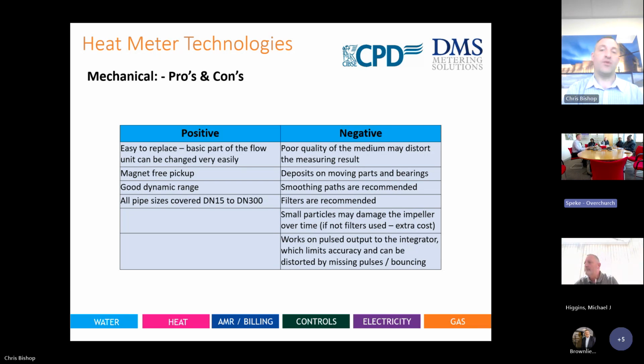With regards to the pulsed output integrator, if you have a high voltage cable near a pulse, there is electromagnetic interference and you have something called bounce back. If that pulse doesn't get through to the actual display calculator, you can miss information as well. So it's just giving you some knowledge on what we see on a day-to-day basis, and why we sometimes argue over why that brand is different to that one. It's more or less the design and the approval that's quite important to us and really important to the client. Obviously, that's the whole point of what we're trying to train people on.